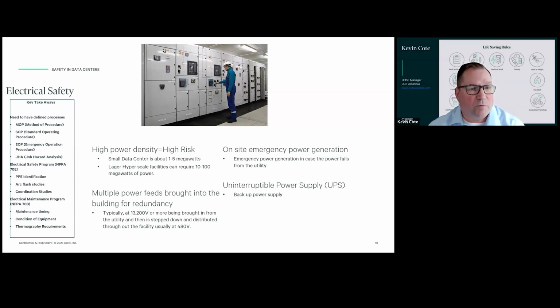And then we also have, which is a little bit newer now, we've always had 70B, but now it's incorporated into our rulings. And so now you have NFPA 70B. And 70B is the electrical maintenance program. And that defines what a maintained electrical system is, what it looks like, what it has, what the main components are, what the maintenance schedule is, and defines what that condition is. It'll define how often you need to do thermography, how often you need to do oil changes, if there's oil changes needed, how often you have to certify your breakers. Those types of things are all things that it would identify.